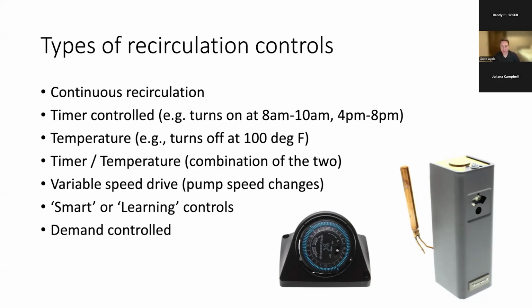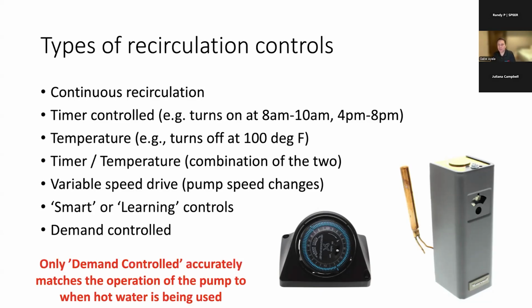Last but not least, there's demand controlled recirculation. And of all of these control strategies, only the on-demand system accurately matches the runtime of the pump to when hot water is being used. So it has the most amount of pump off time. You get all of the benefits of a recirculation system in terms of fast hot water, in terms of water savings, but you don't have any of the energy losses or the wear and tear associated with recirculation systems.